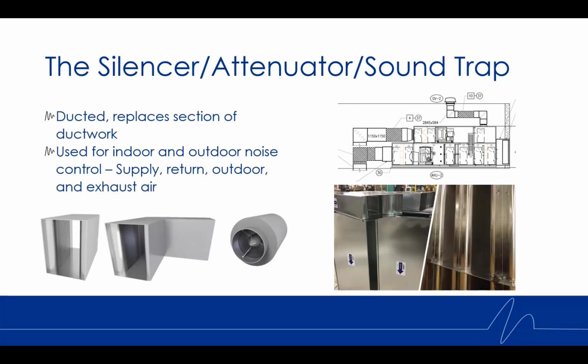And so those rounded sections just in the middle of the silencer here, that is a rounded sheet metal nose. We have some perforated sheet metal here, and then in between the outside casing and that perforated sheet metal, that's where we have what we call an acoustic media. We typically will use a fiberglass, but we have a couple other options as well. And that fiberglass in there is going to absorb any excess noise in the system.